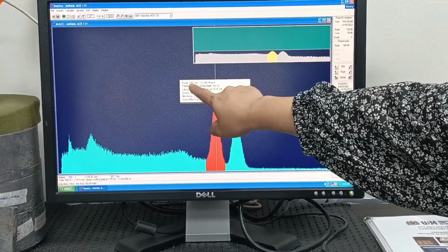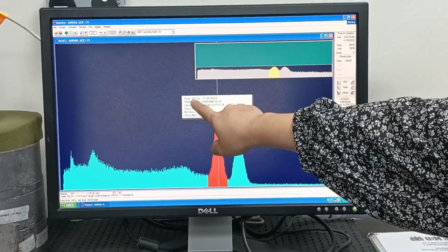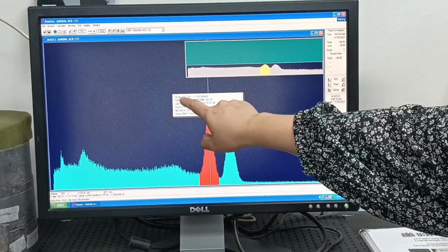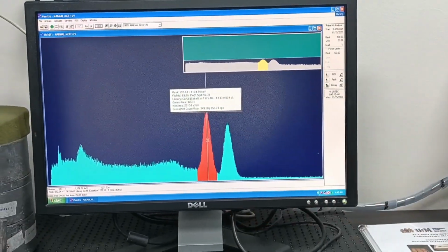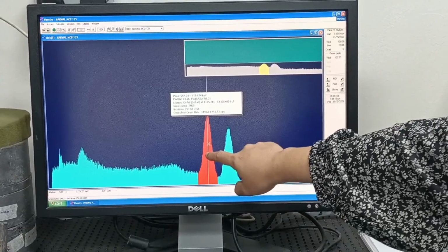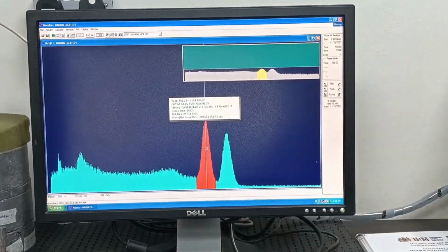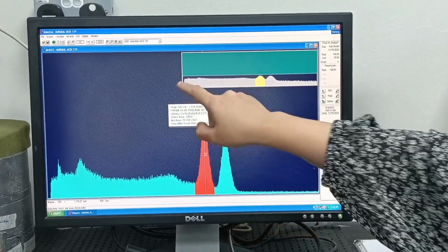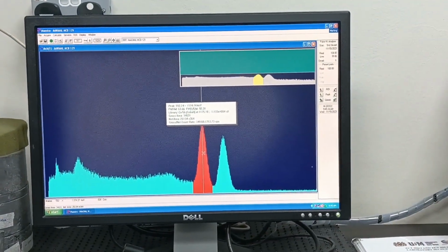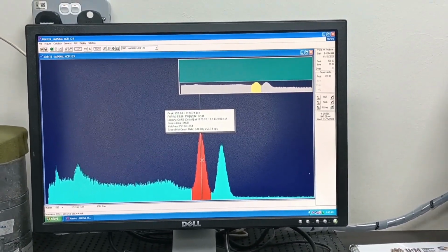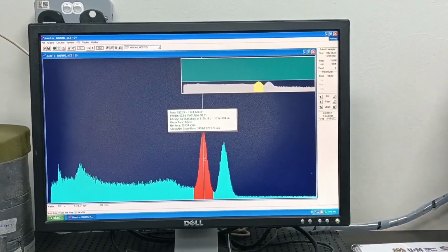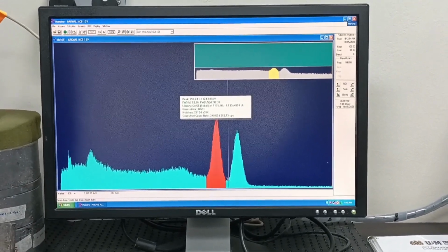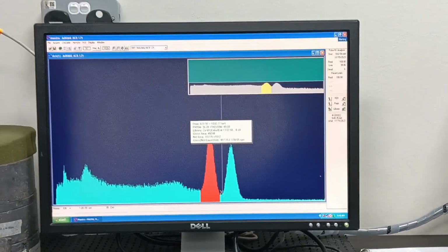It will be displayed here as 592.24, which would be the middle of this peak, the 1170 peak. So you know the peak number, the middle channel number, and you know the energy. The energy is 1170. So that's your data. And you repeat the measurement about 4 to 5 times. And then you analyze the next peak. Alright, so you'll be analyzing the next peak.